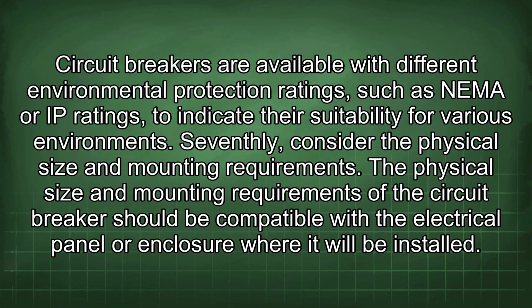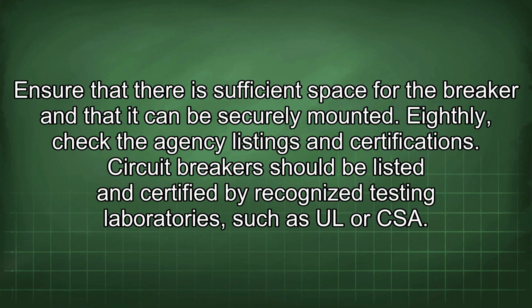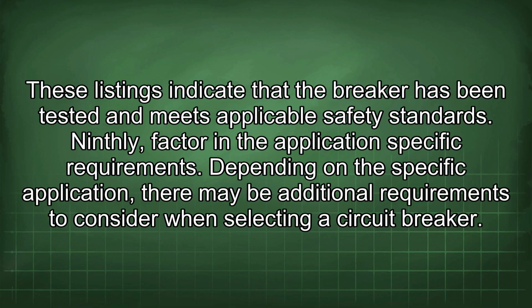The physical size and mounting requirements of the circuit breaker should be compatible with the electrical panel or enclosure where it will be installed. Ensure that there is sufficient space for the breaker and that it can be securely mounted. Eighthly, check the agency listings and certifications. Circuit breakers should be listed and certified by recognized testing laboratories such as UL or CSA. These listings indicate that the breaker has been tested and meets applicable safety standards.